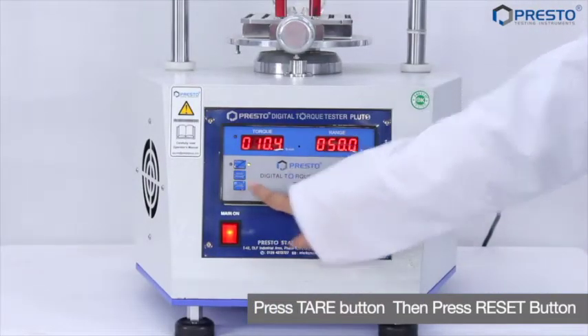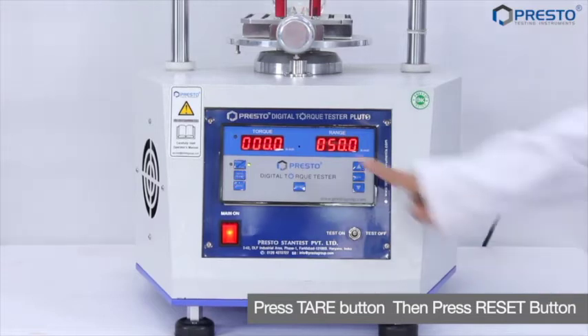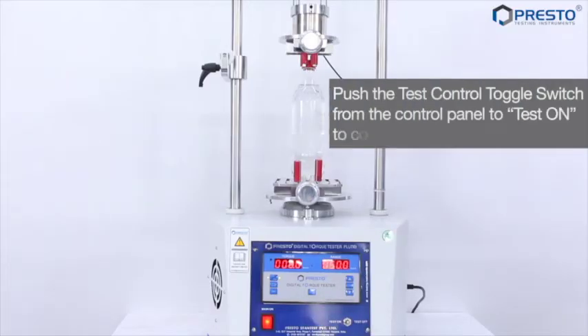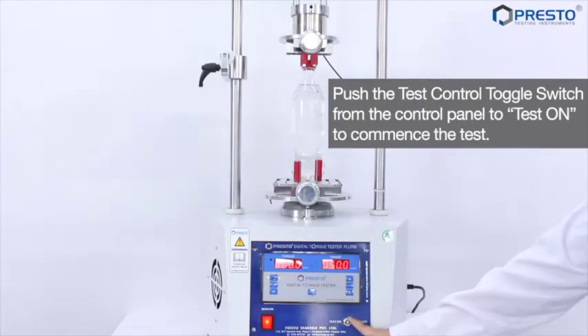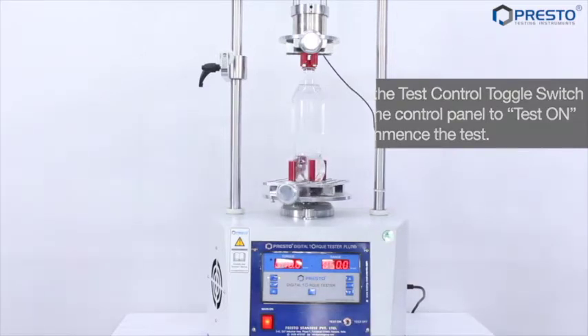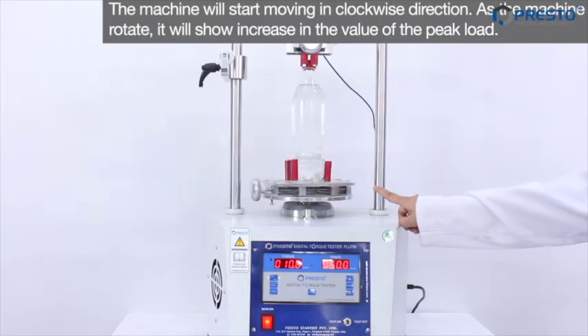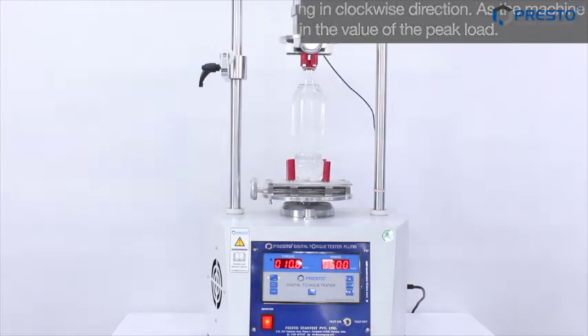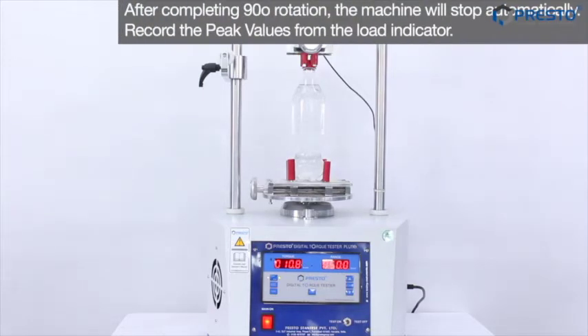Press tare button, then press reset button. Press the test control toggle switch from the control panel to test on. The machine will start moving in clockwise direction. As the machine rotates, it will show increase in the value of the peak load. After completing 90-degree rotation, the machine will automatically stop.